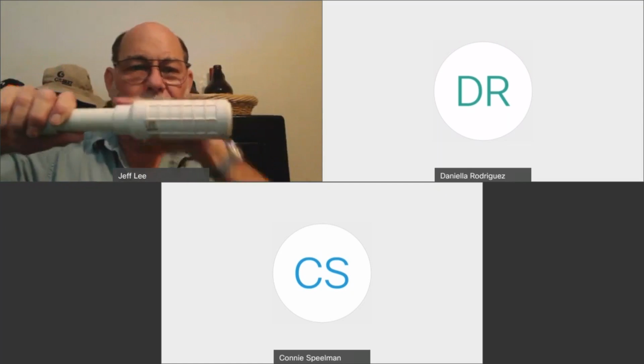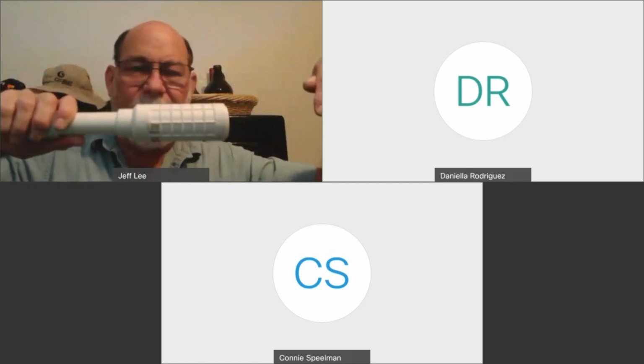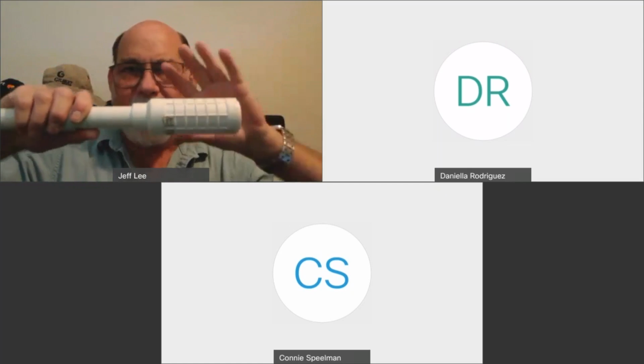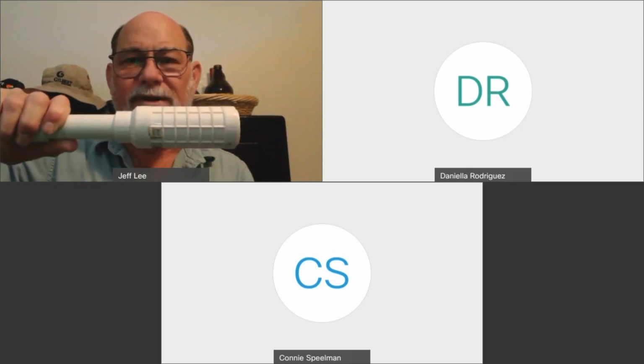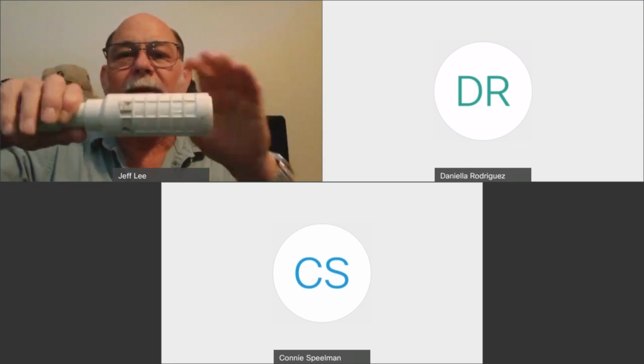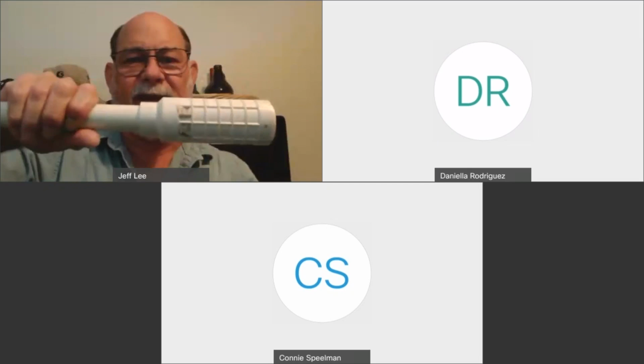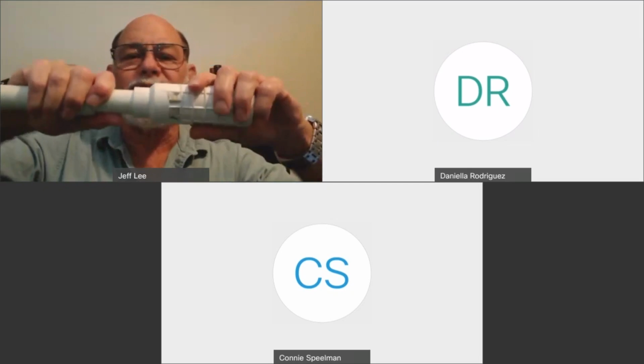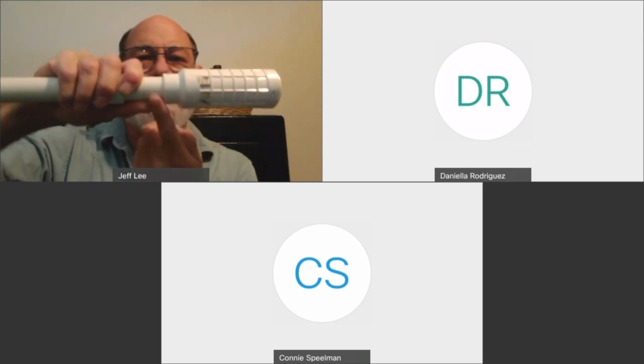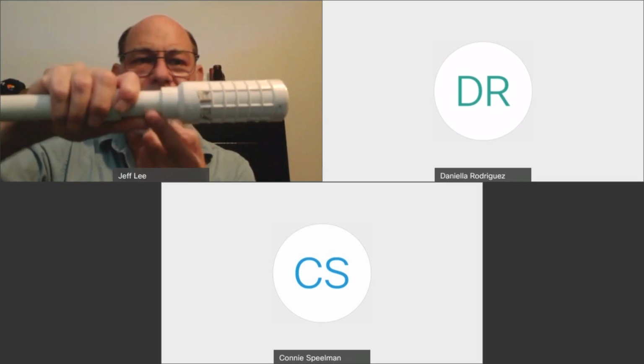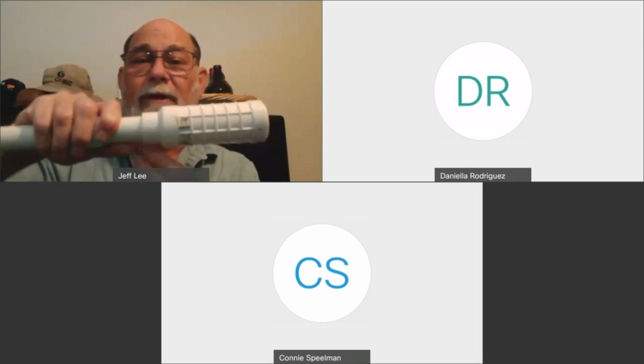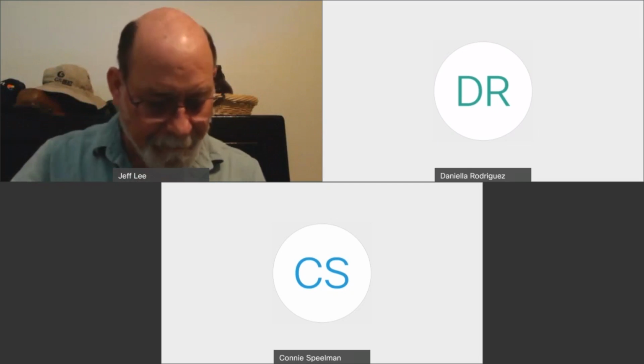Some people will say you've got to make sure it's extending in the direction of the water. That's ridiculous. If you've got a good glue joint on both sides, you're fine. But it is very important that it's fully extended. If you only partially extend this, it doesn't make the seal, and you've got a leak right here. Not a huge leak, but it will leak every time you run the system.